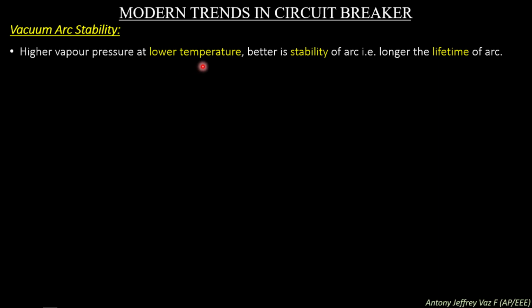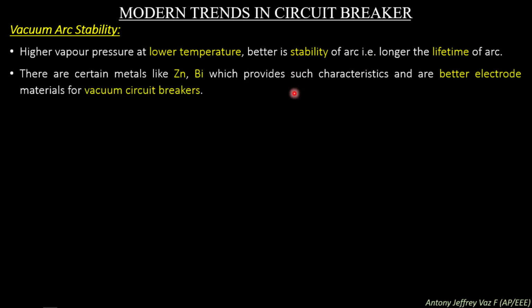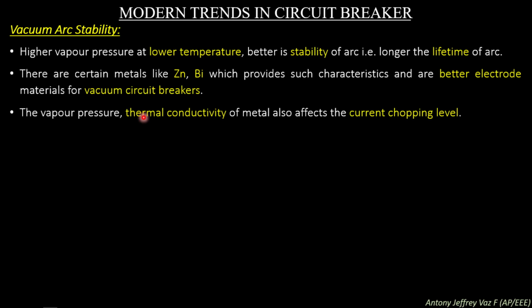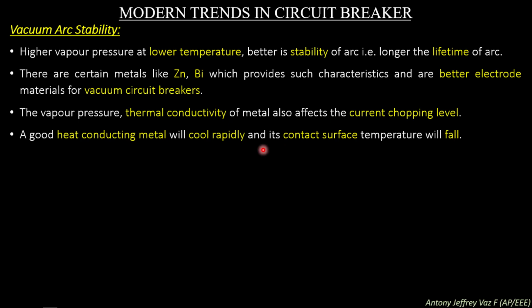The higher the vapor pressure at a lower temperature, the better is the stability of the arc and the longer the lifetime of the arc. There are certain metals like zinc and bismuth which provide such characteristics and are better electrode materials for vacuum circuit breakers. So zinc and bismuth have very good characteristics for a vacuum circuit breaker. The vapor pressure and thermal conductivity of metals also affect the current chopping level. A good heat conducting metal will cool rapidly and its contact surface temperature will fall. So when a heat conducting metal is used, it will cool rapidly and the contact surface temperature will fall.